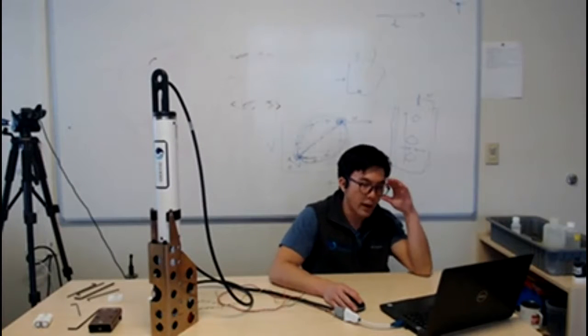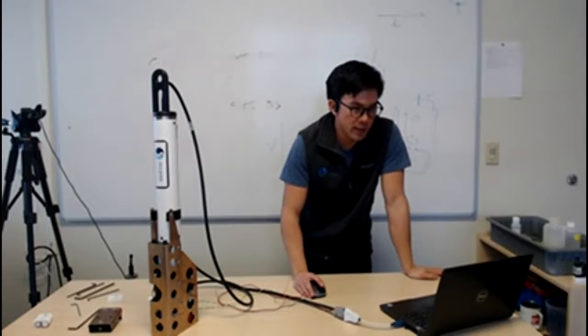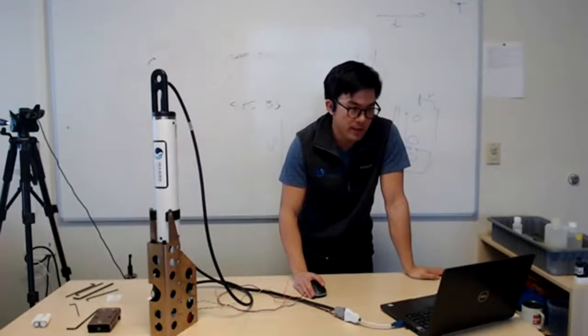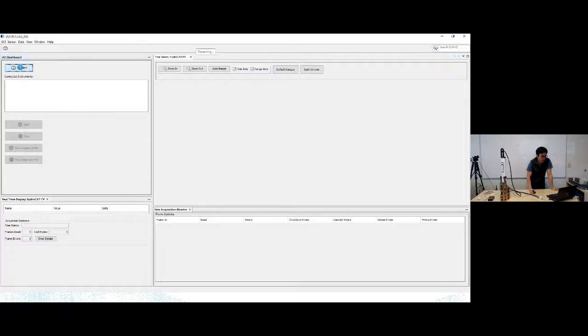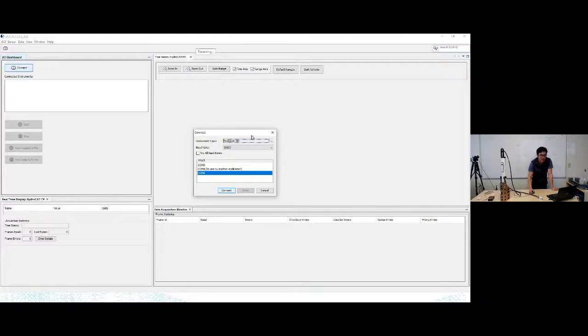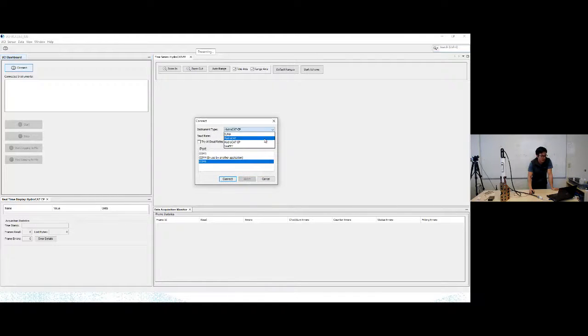So if this is your first time firing up UCI, this is what it's going to look like. On the left here, you have this UCI dashboard. And so what we're going to do is click on this connect button. As mentioned before, UCI connects to multiple different instruments. And so what you'll want to do is choose the instrument type that you're connecting to, in this case, a HydroCAT EP. Choose the baud rate. Default baud rate is 19200, but if you don't know or if your instrument is not connecting, you have the option to click this box to try all baud rates. If someone has changed the baud rate on your instrument and you weren't aware, you can do this and it will connect.